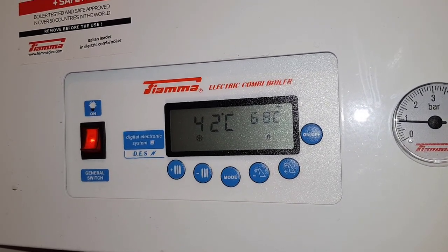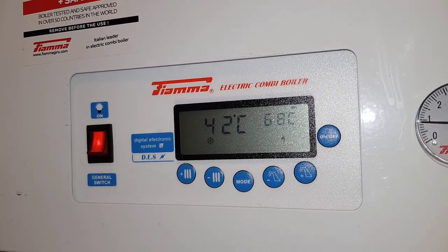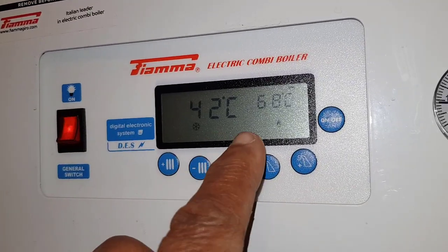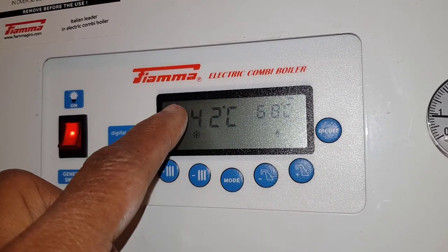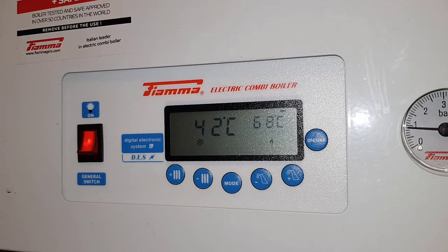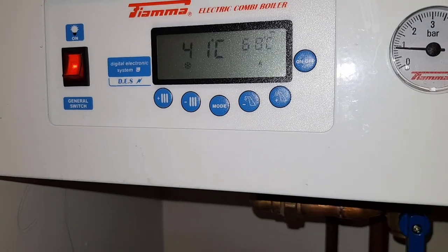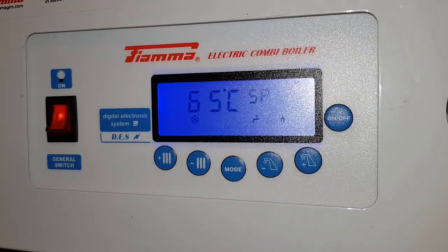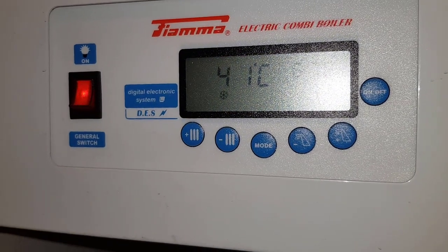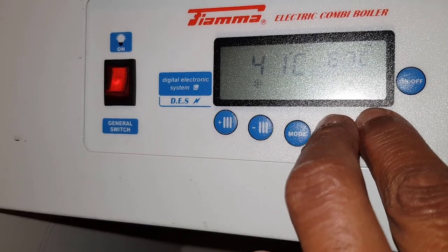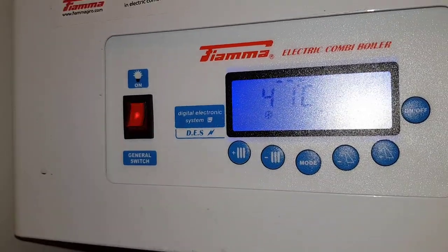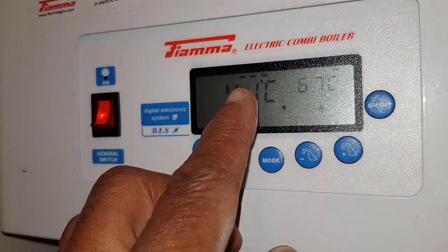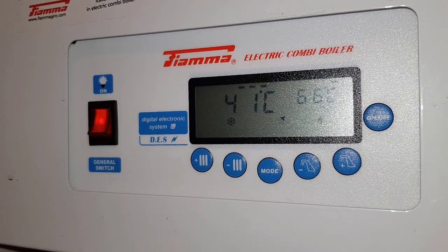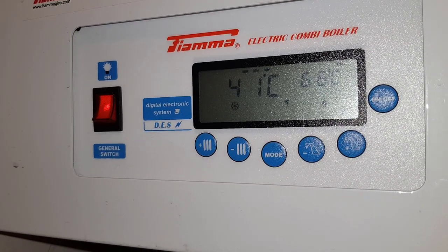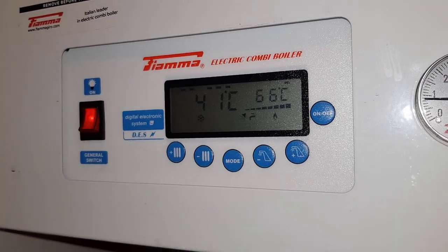So the tap is now running. Right now the pump should be running, as I said before. That bar should go across. The main heat exchanger should start heating, but it's not. But if I press these two together like that, then the hot water tap's flashing. Oh, it's not done it now. Let's try it again. Yeah, so the main heat exchanger is coming on now, but the pump has not started yet, which it should have. Oh, it's just starting now. So that's what it should do.